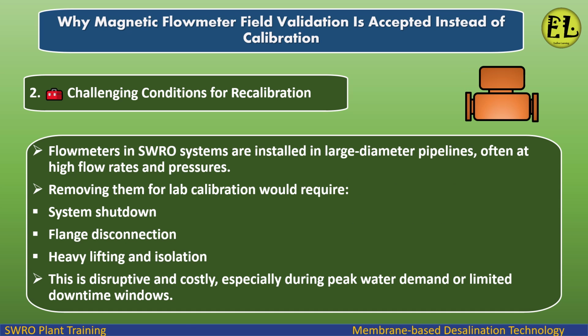Challenging conditions for recalibration. Flow meters in SWRO systems are installed in large diameter pipelines, often at high flow rates and pressures. Removing them for lab calibration would require system shutdown, flange disconnection, heavy lifting and isolation. This is disruptive and costly, especially during peak water demand or limited downtime windows.